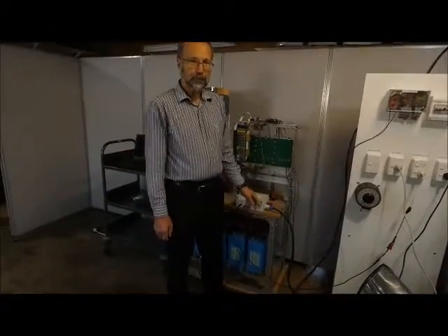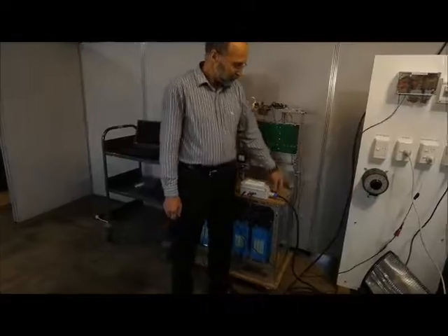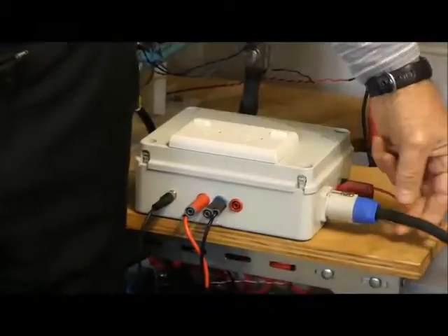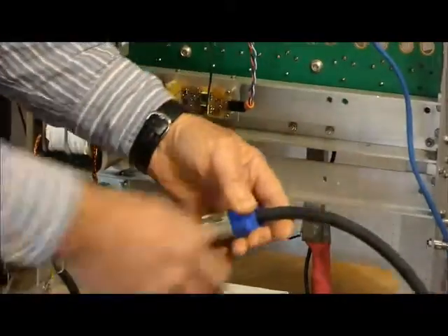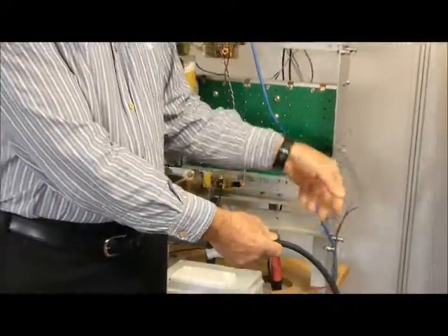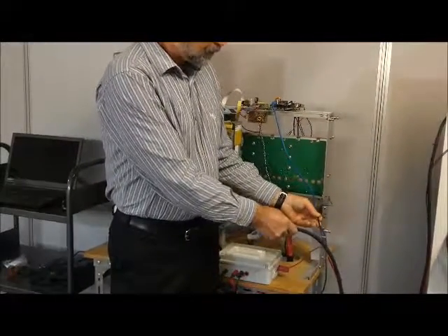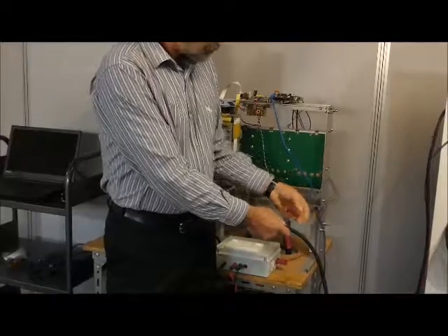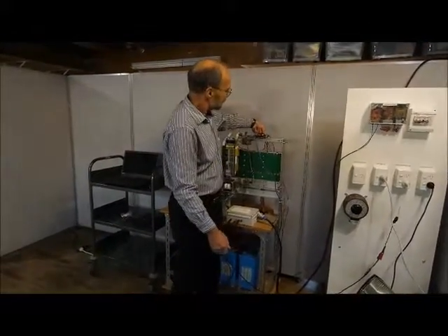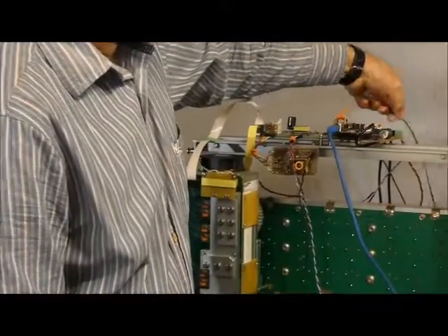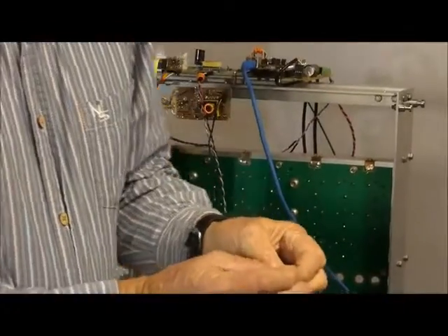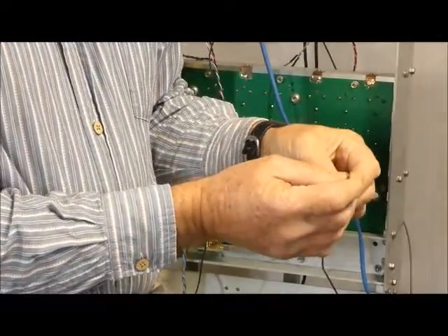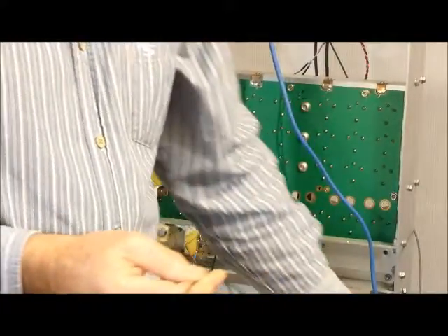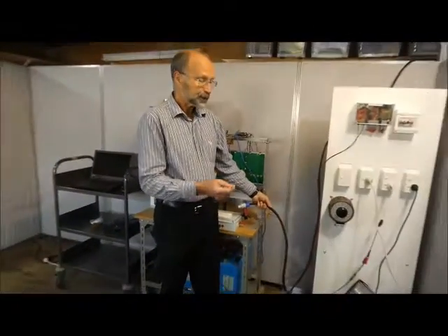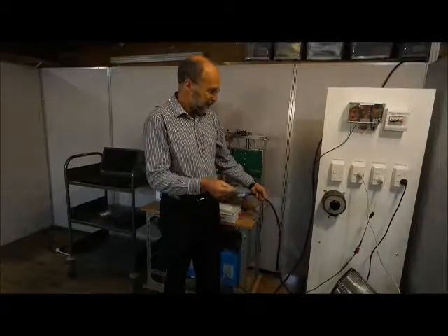This is the connection from the inverter to the grid interface. For demonstration purposes we have a flexible cable with a plug-in connection, but in a real installation this would be fixed wiring in the house. Here we have the communications link from the grid interface to the inverter, done with low-cost plastic fibre optic cable with a simple screw connector. The cable can be cut with a sharp knife. There are no special installation tools required, and it can be run along with the mains cable between the inverter and the grid interface. There is no chance of electrical interference.